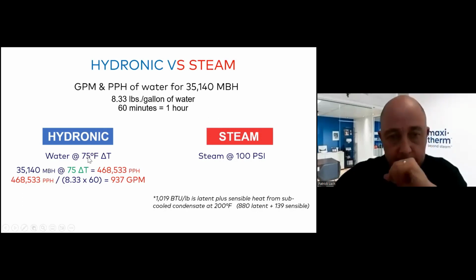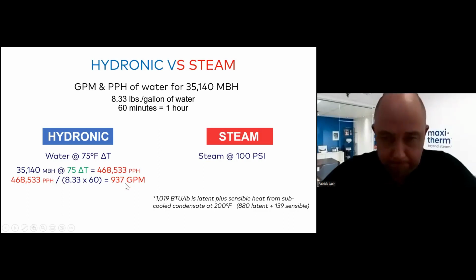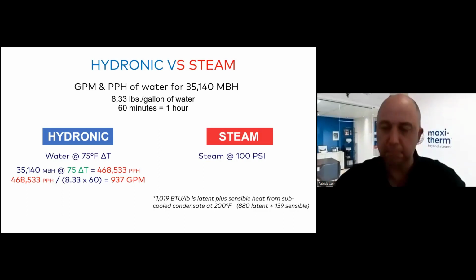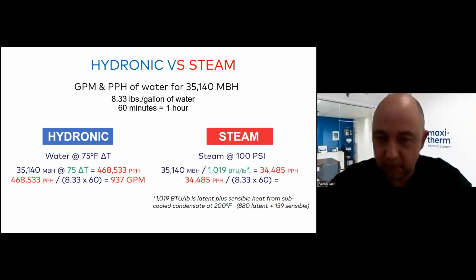So the rise was 75 Fahrenheit on the primary loop. Okay, they will need 468,000 pounds per hour of mass flow and 937 GPM. If they had considered steam, even a 100% closed loop design, let's say, they would need only 34,000 pounds per hour of mass flow and only 69 GPM.